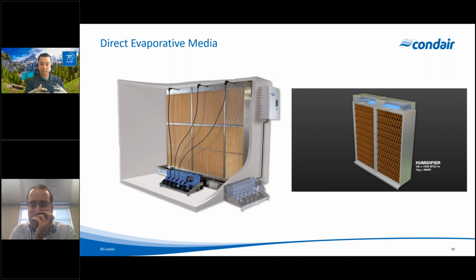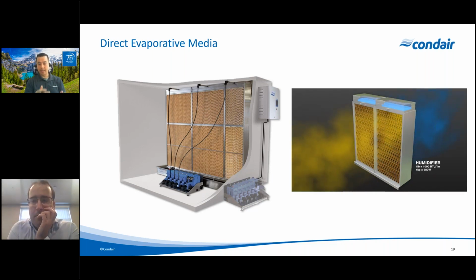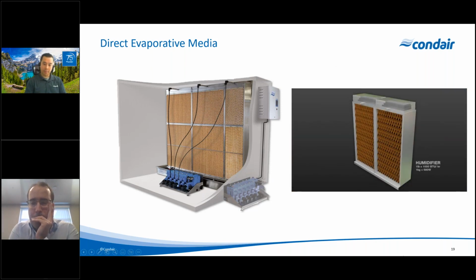We effectively take potable water or treated water, we pass that over a wetted pad, and then the hot, dry air goes through that pad. All the evaporation takes place within the pad itself, and then we have cool, humidified air downstream from that. So with all of these systems, every pound of water that we evaporate is about 1,000 BTUs of cooling. Just something to keep in mind there.